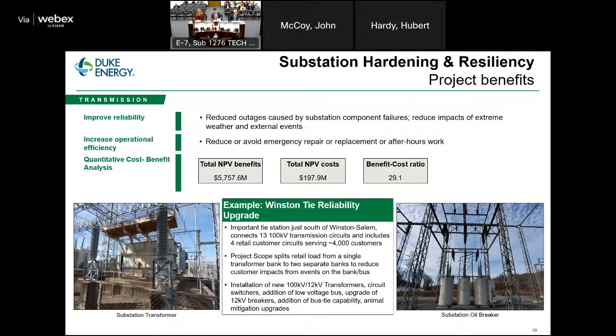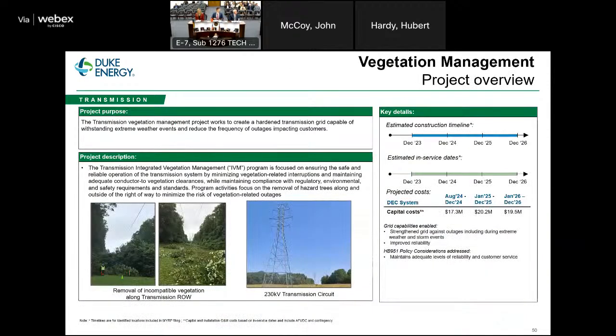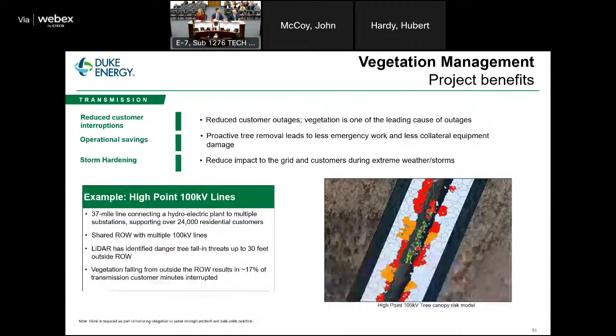All right, I'll move on. Our vegetation management project scope, similar to what Mr. Guyton spoke to, is focused on hazard trees or danger trees, as they're sometimes called, but these are trees outside of the right-of-way. I did mention this is the number 1 driver of customer minutes interrupted from the transmission system, about 17% of transmission outages from trees from outside the right-of-way. So we are specifically targeting those trees through an aerial inspection program. And we're actually creating what we call a tree canopy risk model. I'm going to jump to the next slide so you can see an image of this.